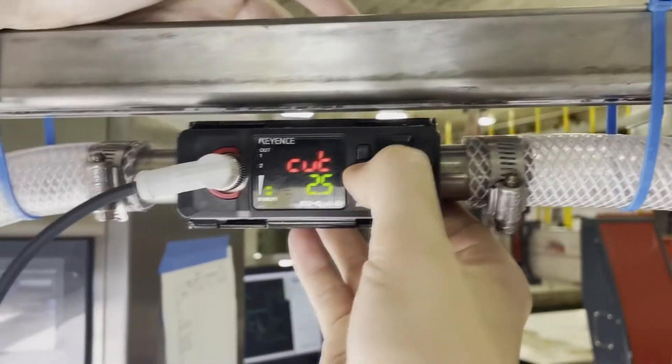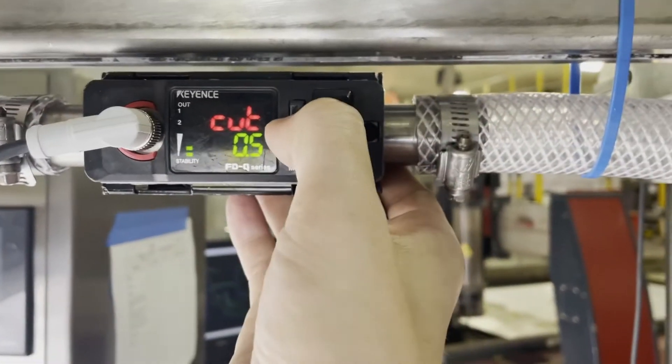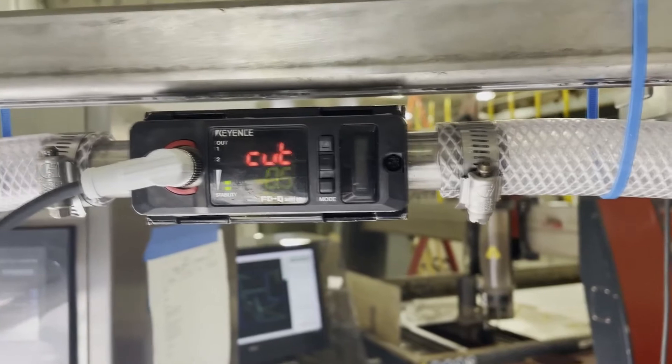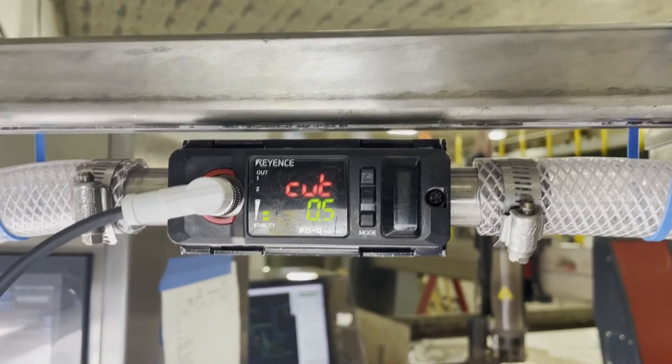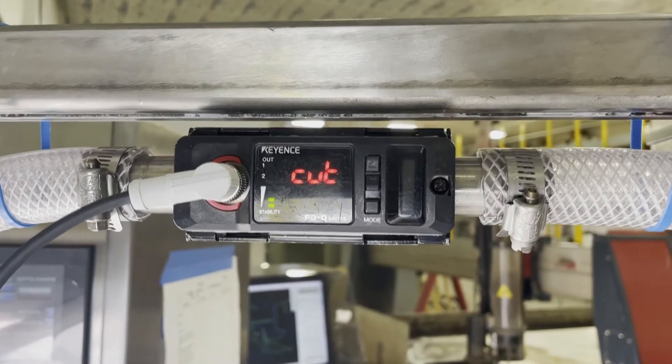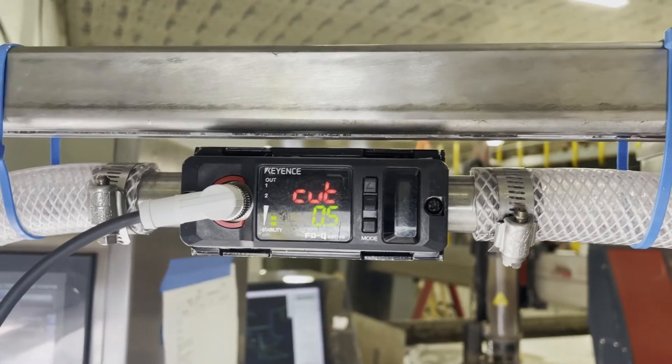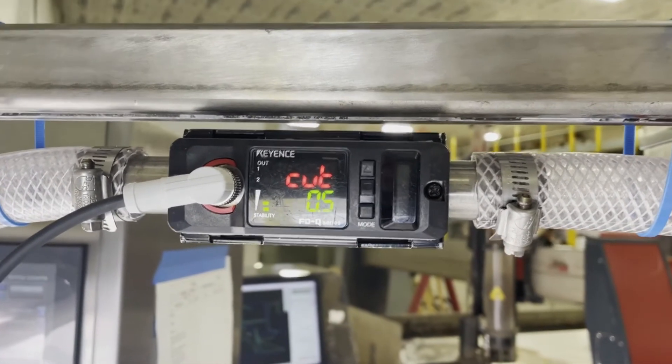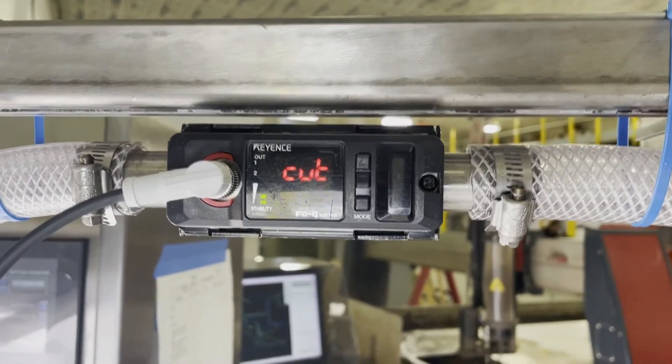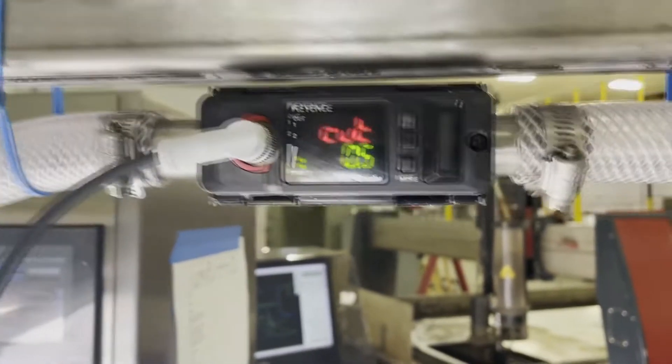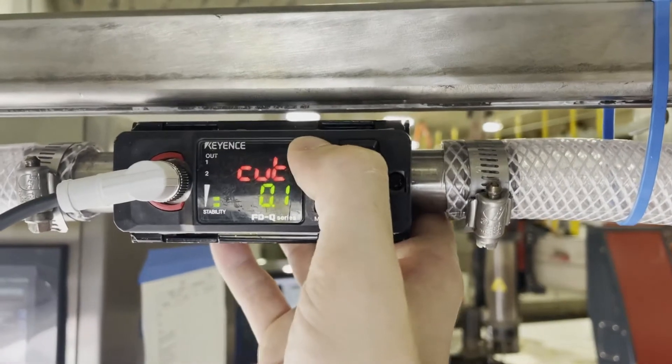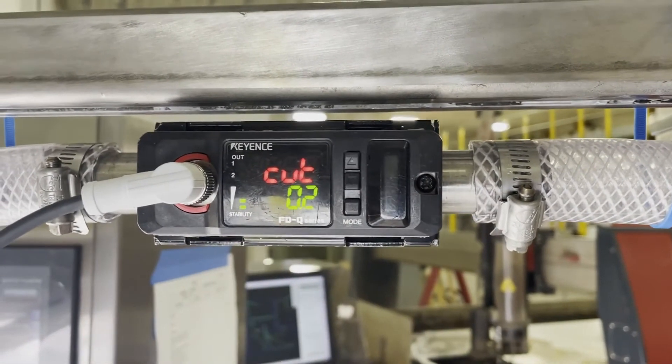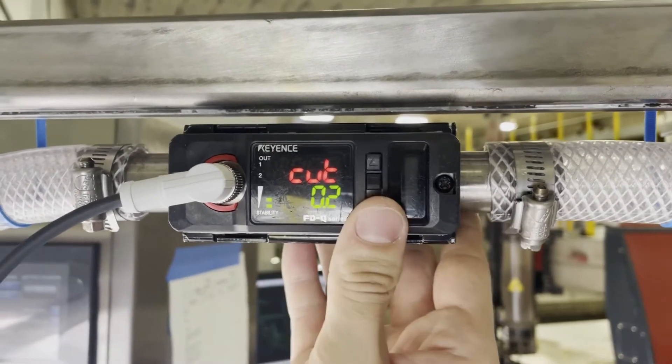Now your cut flow rate, this is important. This is in regards to what do I want it to ignore below 0.5 liters per minute of flow rate or below I want to read a zero. This is so you don't get any false triggers if the liquid maybe moves slightly back and forth. Does that make sense? Yeah. But that one, we don't want to put it to zero because sometimes I can miscount if I'm on zero. So I normally put it to 0.1 or 0.2. 0.1. Okay.